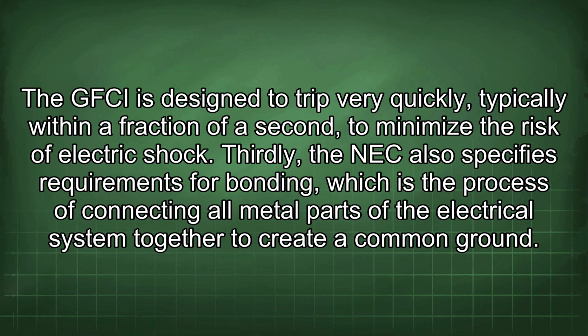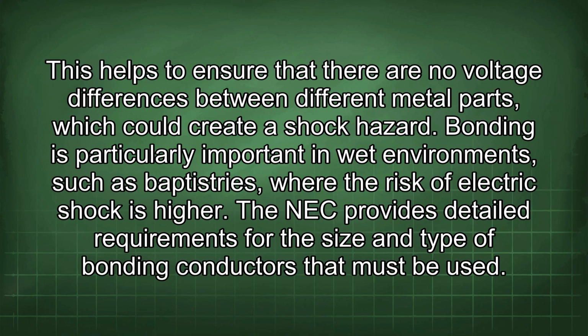Thirdly, the NEC also specifies requirements for bonding, which is the process of connecting all metal parts of the electrical system together to create a common ground. This helps to ensure that there are no voltage differences between different metal parts, which could create a shock hazard. Bonding is particularly important in wet environments such as baptistries, where the risk of electric shock is higher. The NEC provides detailed requirements for the size and type of bonding conductors that must be used.